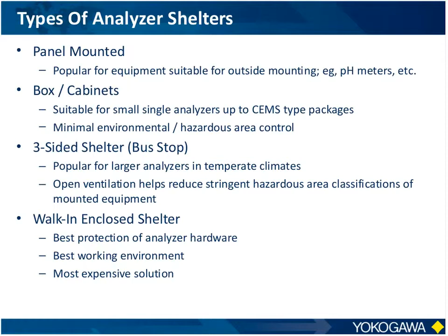and so that can make meeting area classifications and hazardous area classifications a lot easier and cheaper. And then finally, there's the full-blown walk-in shelter, whether it's a steel building or something like that, where you walk in through a door and all the equipment's mounted in there. It's temperature controlled, often purged and ventilated, and provides a great work environment for the analyzers and the technicians, but obviously it can quite frequently be the most expensive option. So when you look at your different options, you need to weigh the benefits versus the cost.